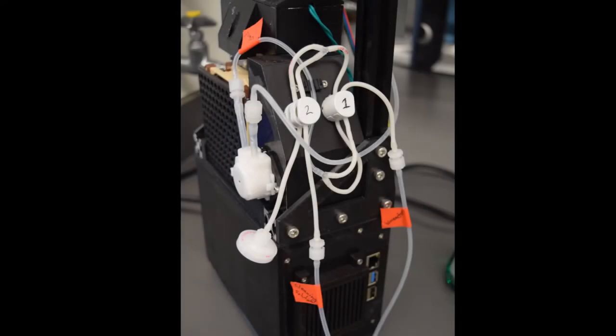Next, connect these fittings properly and insert the pinch tubing into the valves. The peristaltic pump should be fitted with two female 1/4-inch luer lock barbs. The pump section of the tubing is connected to the left inlet of the peristaltic pump. This tube is then inserted into the fluid sensor at the valves and then winds towards pinch valve number one, which is on the right side. The bioreactor or source branch goes in the front slot of valve number one, and the branch going to the other sections is inserted into the back slot of valve number one. For the other two branches, the one with the sterile filter should be inserted into the back slot of valve number two, and the cleaning solution branch into the front slot of valve number two.